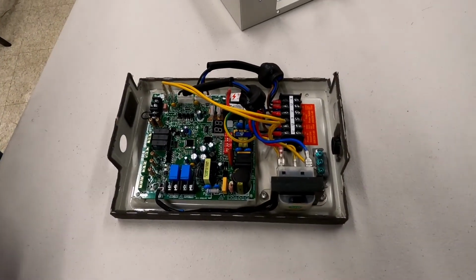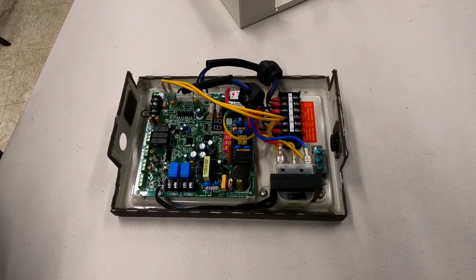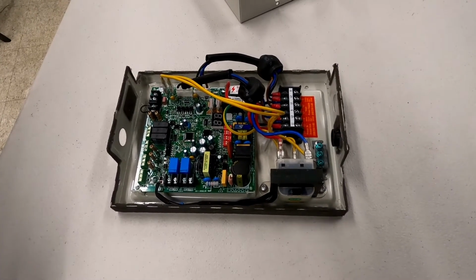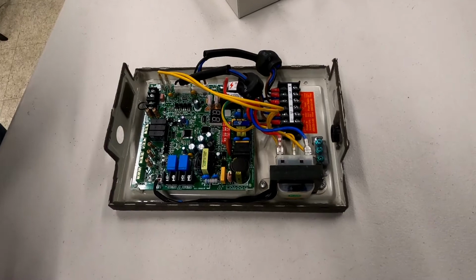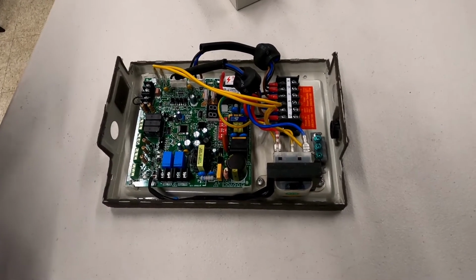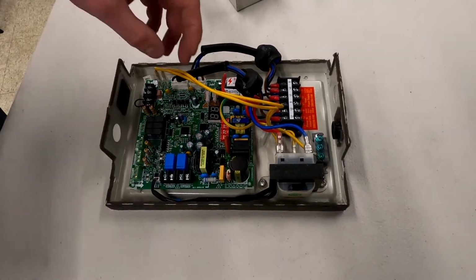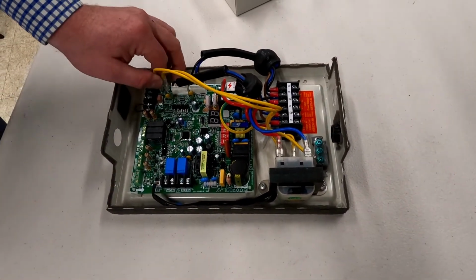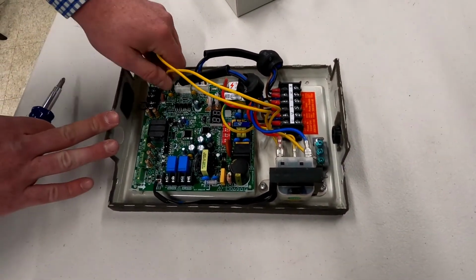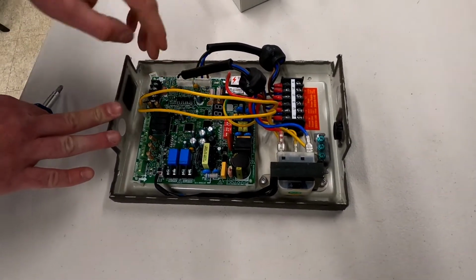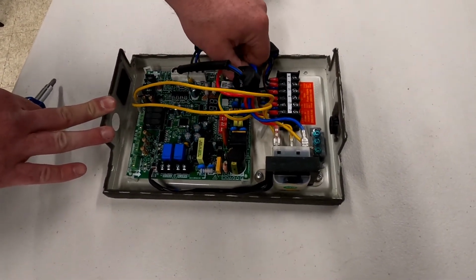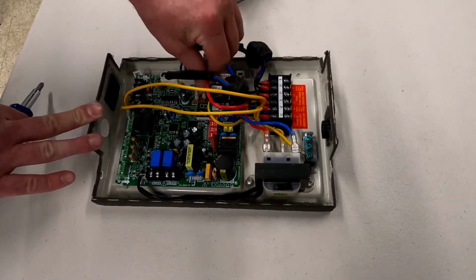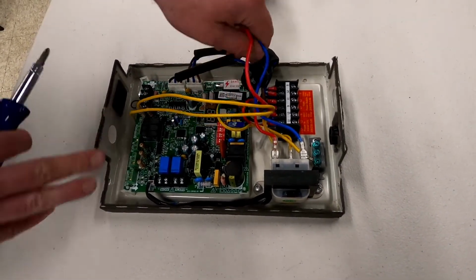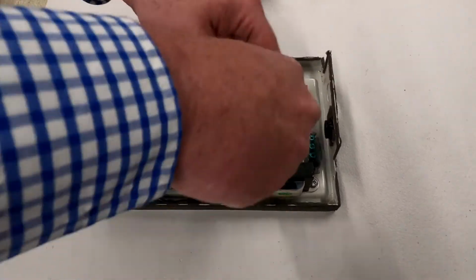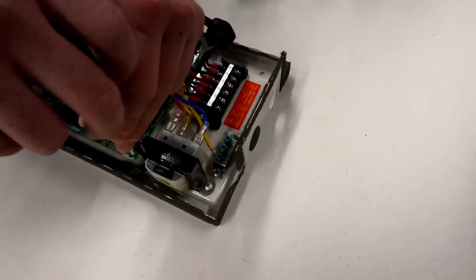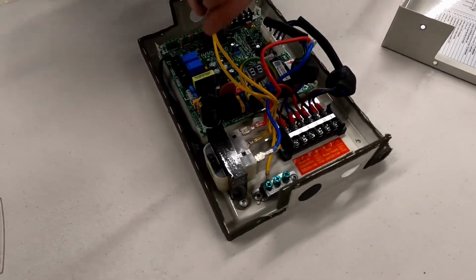When a 24-volt interface kit is paired with a conventional fan coil, we need to remove the transformer that comes inside the interface kit. The 24 volts will be supplied from the transformer in the air handler. So we need to pull our wires off of CN16 and CN17, which is 24 volts from the transformer. And then we need to pull our high voltage wires off of CN2 and CN1. Then you want to unscrew the transformer and remove it from the interface kit.